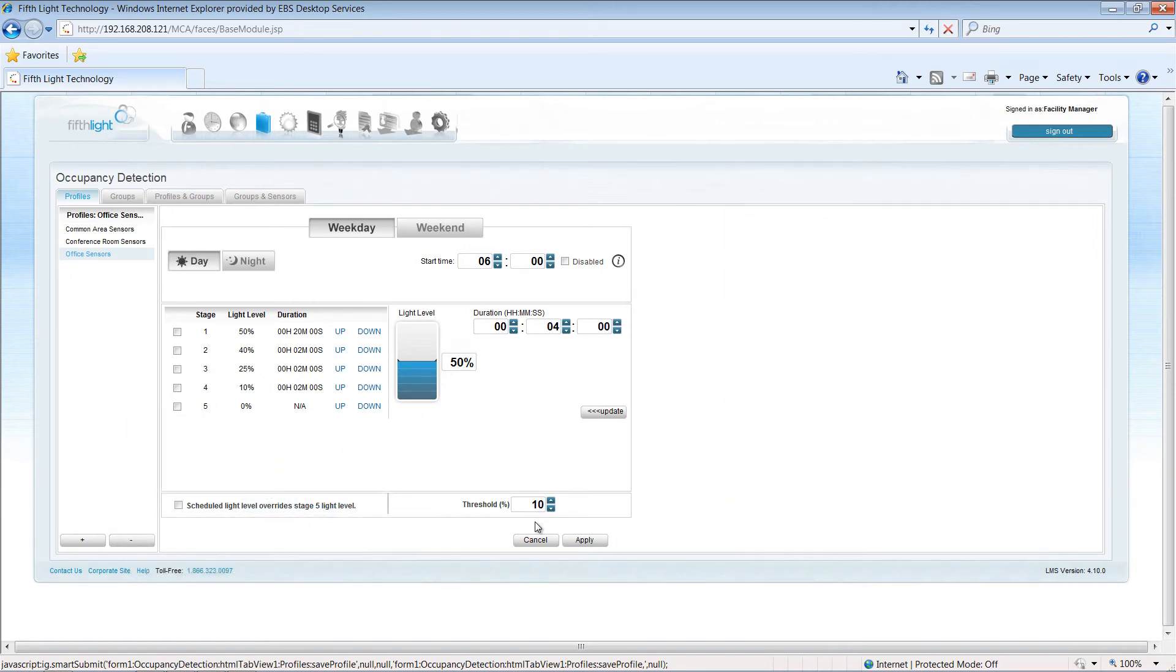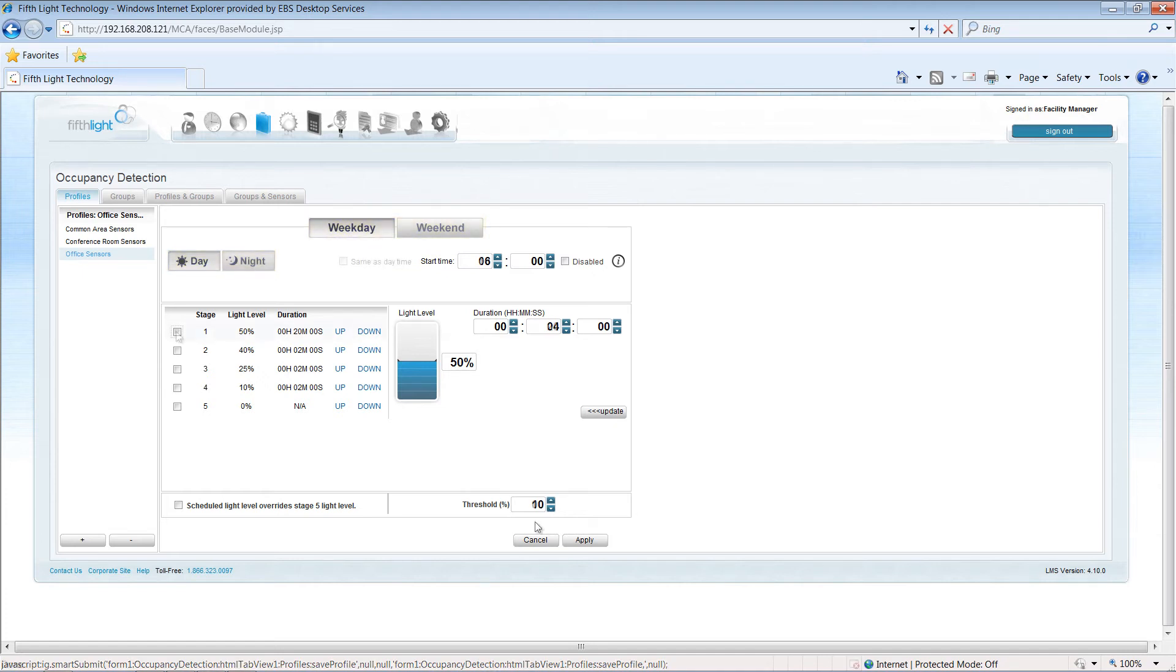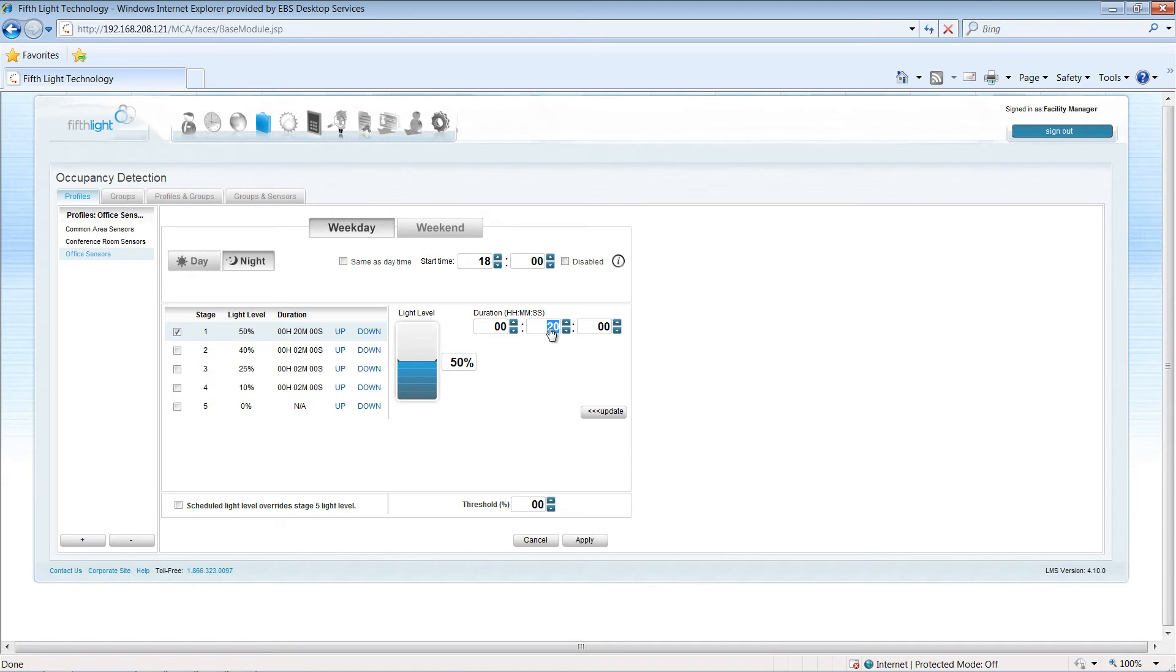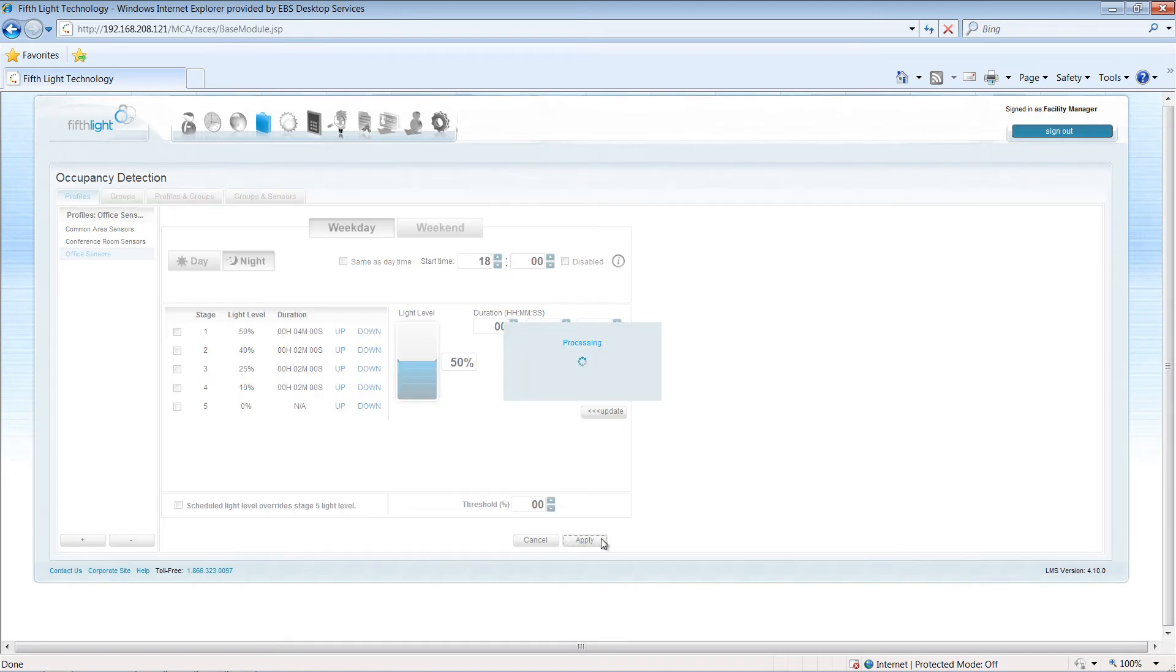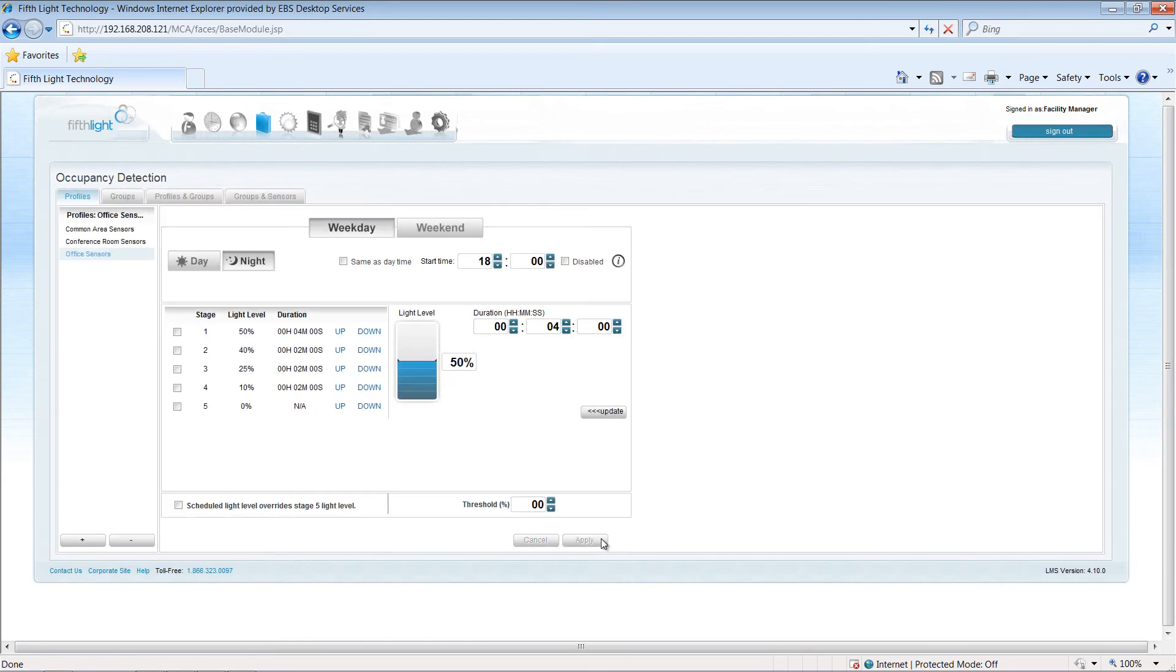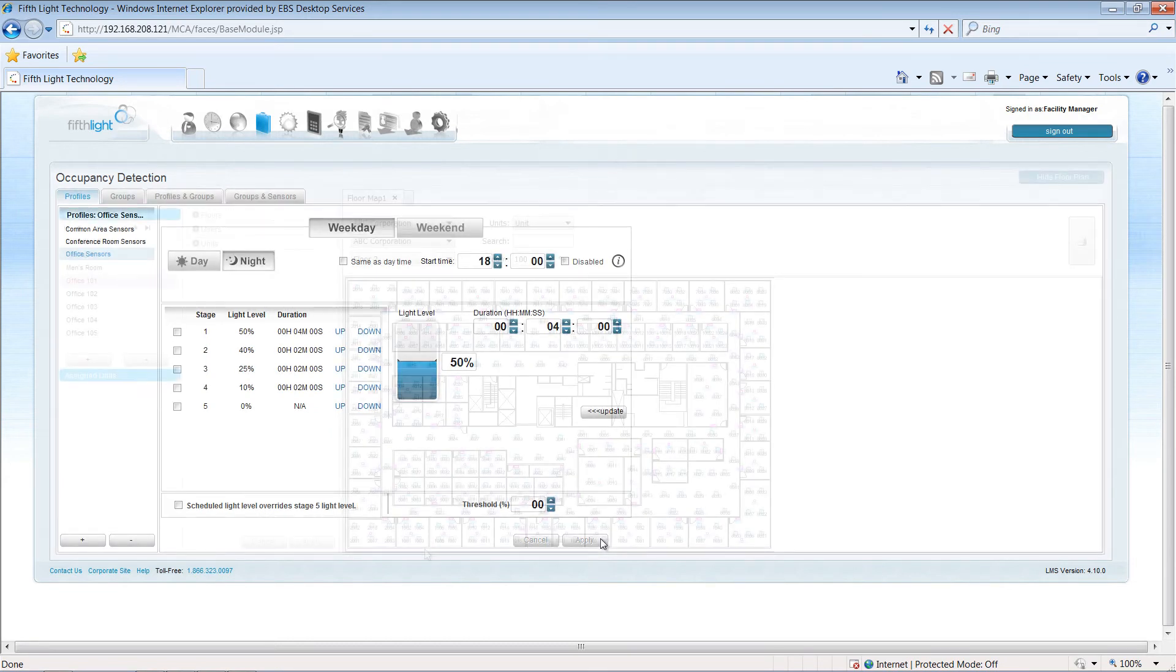For additional savings, the occupancy sensor settings can be different from daytime to nighttime and from weekday to weekends. At night and on the weekends, I may want to shorten the timeout period of the sensors so that brief occupations by cleaning crews or by the employee coming in to grab a file do not result in unnecessary energy waste.